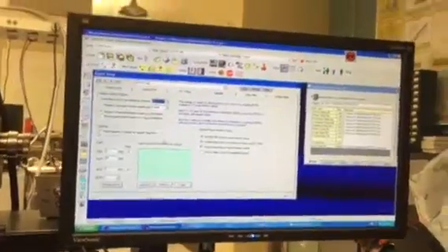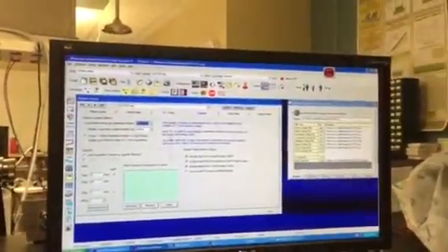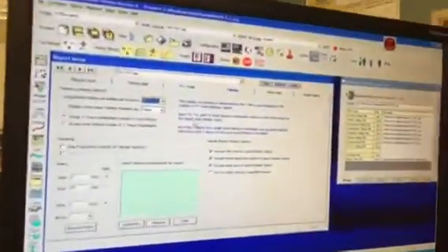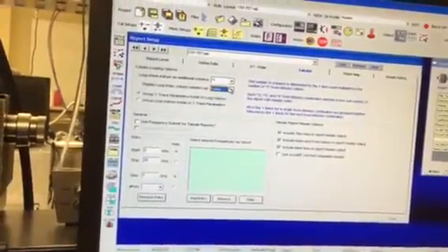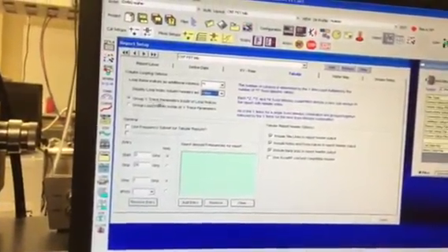Anything we need to change? No, that's all. Some people take data for S parameters higher in frequency than they need it, and then they see where the data gets bad, and they chop it off so they can make nice reports. That's really cool. Display load index. Where is this?